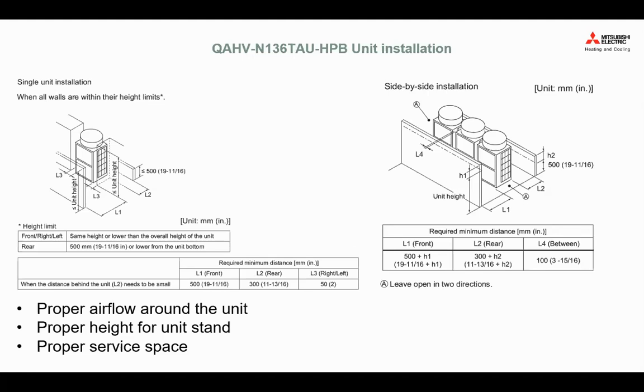However, while doing the design and thinking about the space, you want to make sure there is proper airflow around the unit, so there's no short cycling of air. So basically, the QAHV is going to take the heat out of air, right? So essentially hot air goes in and cold air comes out. If you have obstruction or improper airflow, you may short cycle the cold air, and eventually the performance may not be as good as expected, just because the airflow is not being properly distributed for the condenser for the refrigerant to suck the heat out of the air.